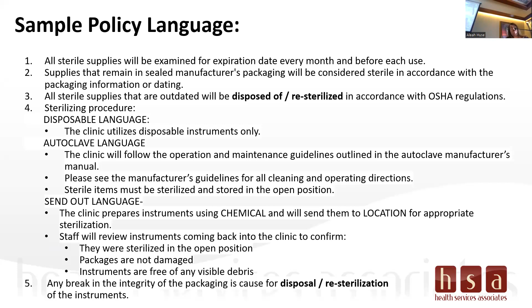Now, here are some cautions. We already talked about the difference between a disinfectant and a sterilization process, making sure that we understand what that chemical can do and how it accomplishes its goal. And then the other thing I would look at is, where are you handling these really high level chemicals? Is it in a little tiny closet with the door closed, locked, and there's no ventilation in that space at all? I would be really careful of that, because it can be an OSHA exposure. I would be very cautious about where you're storing your chemicals, and where the tub is and instruments are soaking. Be sure it's in a well ventilated area and you're hitting the target of what the manufacturer requires for ventilation.